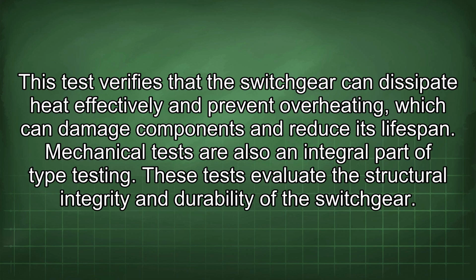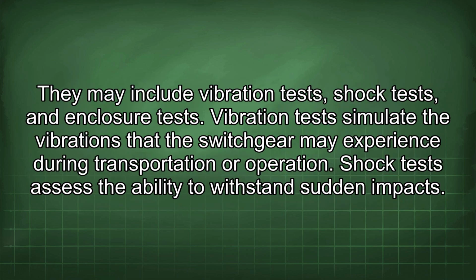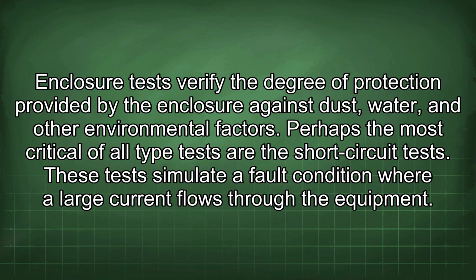This test verifies that the switchgear can dissipate heat effectively and prevent overheating, which can damage components and reduce its lifespan. Mechanical tests are also an integral part of type testing. These tests evaluate the structural integrity and durability of the switchgear. They may include vibration tests, shock tests, and enclosure tests. Vibration tests simulate the vibrations that the switchgear may experience during transportation or operation. Shock tests assess the ability to withstand sudden impacts. Enclosure tests verify the degree of protection provided by the enclosure against dust, water, and other environmental factors.